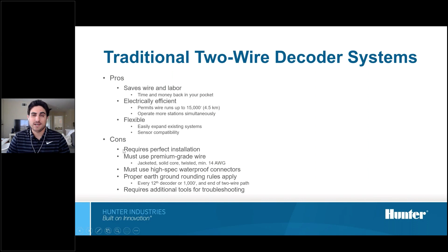I mean, obviously we're running wire long distances underground at varying voltages. We've got to make sure there's no shorts to earth ground, no nicks on those wires, no exposure to earth ground or even the water within the valve box or within the trenches that we're running in. So we've got to make sure up front when we install a traditional two-wire decoder system that it's installed properly, it's grounded properly. You'll see here in the bottom right image, you've got to pound an 8-foot ground rod into the ground, or at least put one of these copper clad plates in 36 inches below the soil about every 12th decoder or 1,000 feet in the two-wire path. Then you've got to ground the end of the two-wire path. Just a lot of additional hardware and a lot of additional installation required to make sure this traditional two-wire system operates as it should be.